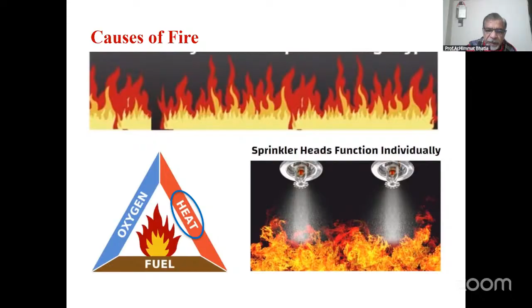Generally, the sprinkler heads function individually. If all the sprinklers opened when the fire erupts, the water would create more damage than the fire, and people would be flooded with water. That is why the sprinkler heads are designed so that wherever the fire erupts and the temperature reaches more than 135 degrees Fahrenheit, which in degrees centigrade is more than 57 degrees, it bursts and starts sprinkling water onto the fire. Sprinkler heads are designed for different heat levels, but the least is 57 degrees plus. So just understand the various fire safety solutions in the high-rise building.